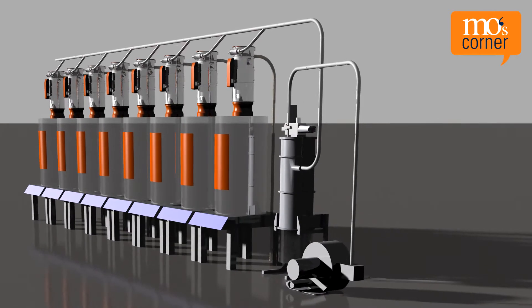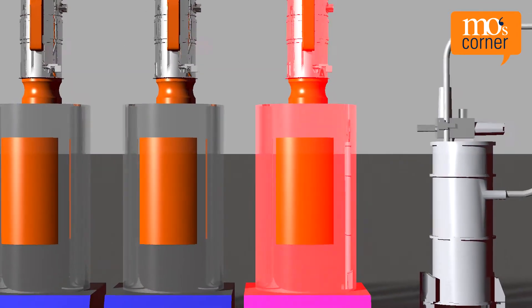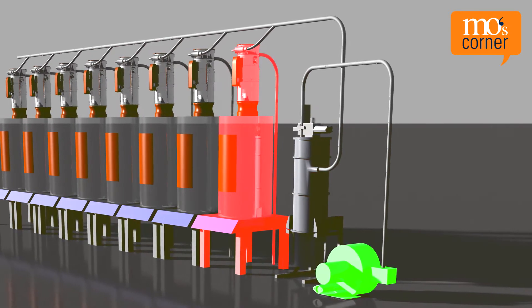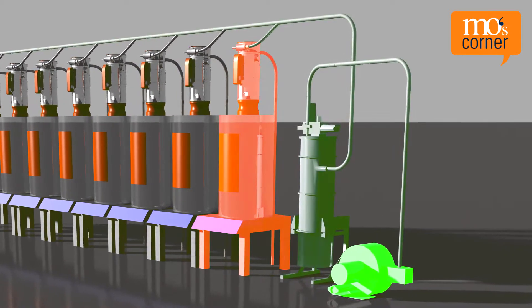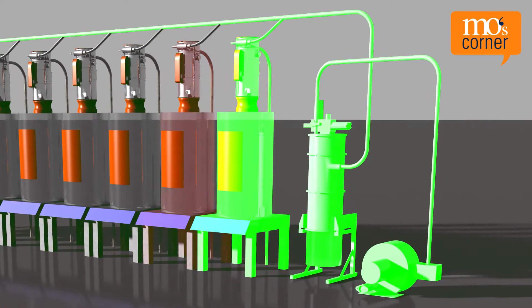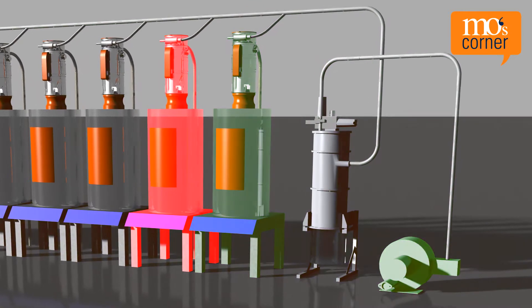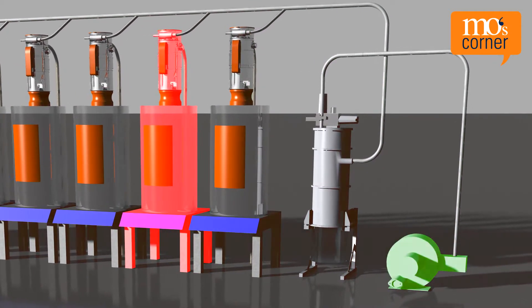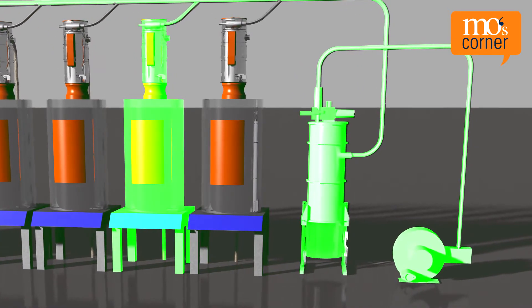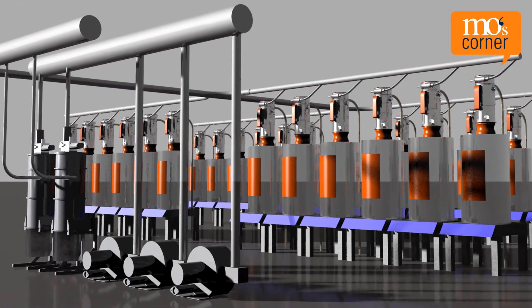This is how a conventional vacuum conveying system works. Conveyor 1 signals a material requisition, then the pump starts up to create a vacuum and the conveying process begins. A second conveyor signals a material requisition. The first conveying process continues to run until finished. After that, the second conveyor receives its material. The second conveying process also finishes, and the vacuum pump lags behind a short time before shutting off.